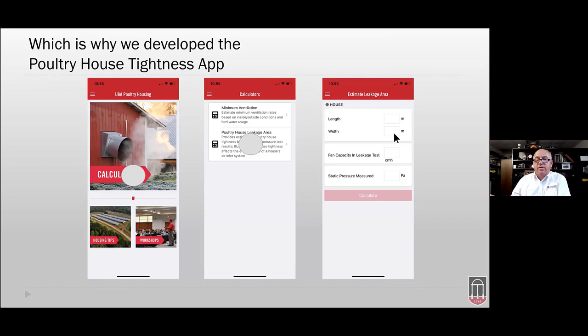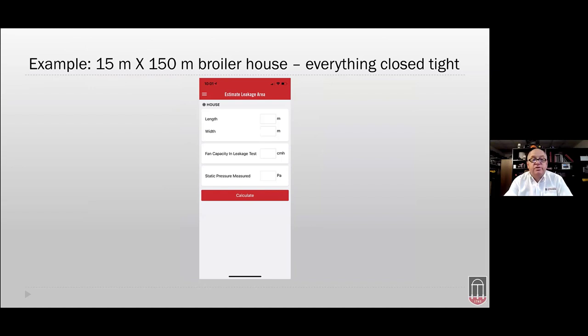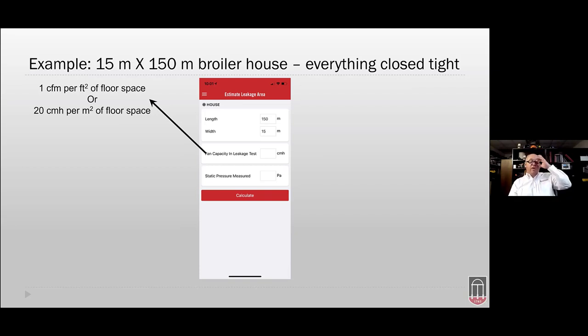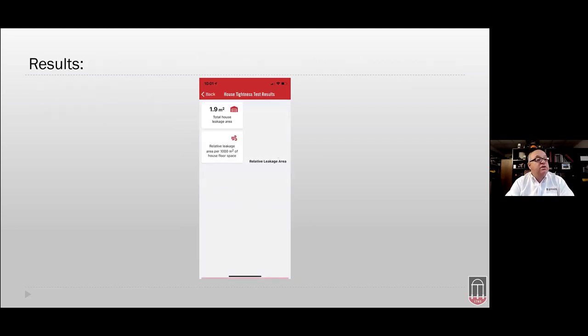The test is simple: close everything up tight, turn on a fan, and measure the static pressure. Input the house length, width, fan capacity, and measured static pressure. For example: a 15 × 150-meter broiler house, everything closed, using three 90-centimeter fans moving 51,000 cubic meters per hour, measuring 30 pascals. Hit Calculate — the app tells us the house leakage area is 1.9 square meters, and the relative leakage area is 0.85 square meters per 1,000 square meters of floor space. That rating shows up as red — a bad rating.